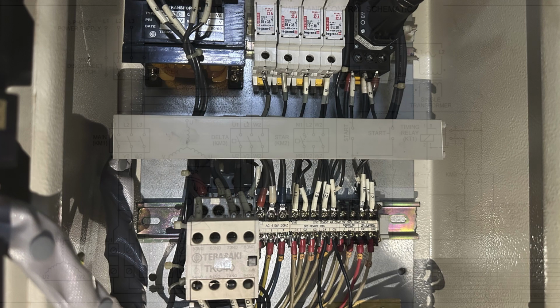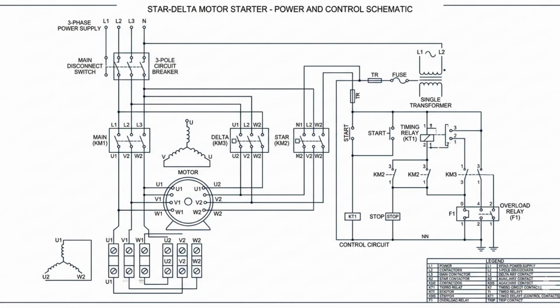In this slide, you can see the power circuit and control circuit of a star-delta starter shown together in a single diagram. At first look, this may seem quite complicated, especially for beginners. In real industrial electrical drawings, circuits like star-delta starters usually include many components such as contactors, timers, overload protection, and multiple control connections. Also remember, in practical electrical engineering, these diagrams are not always shown on a single page. Most of the time, they are divided into multiple pages to clearly represent power circuits, control circuits, and protection systems separately. So don't worry if it looks complex right now. To build a strong foundation, let's first start with the DOL starter, which is the simplest motor starting method, and understand its working step by step.